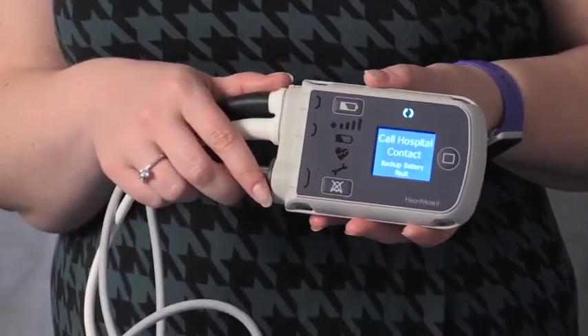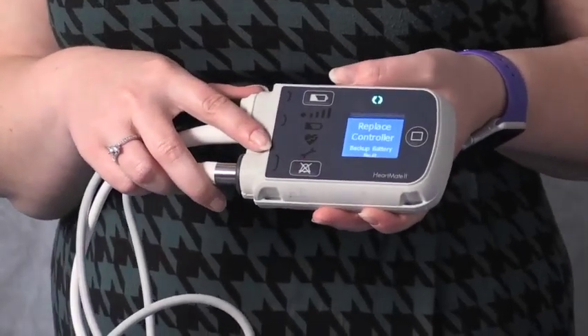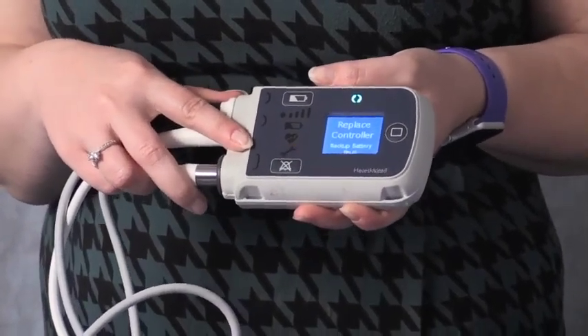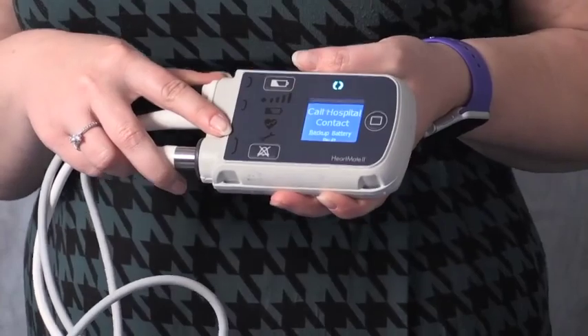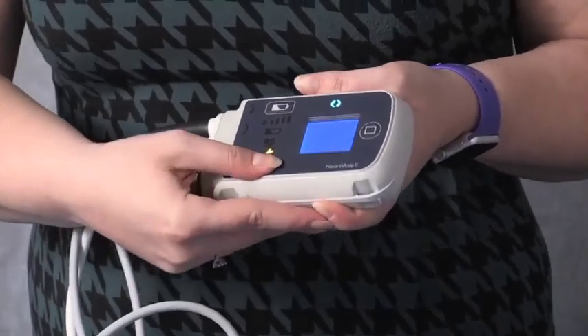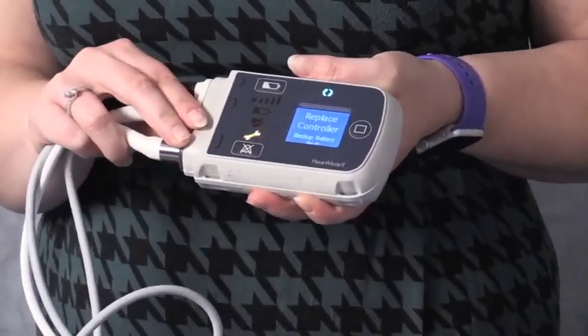So this is what our yellow wrench alarm sounds like. This could potentially be a situation where the patient needs to change their controller at home. The first thing I'm going to do is silence this alarm so that we can talk over the phone. The next thing we need to do is to find the patient's backup equipment. They should have a backup controller and 2 extra fully charged batteries handy.